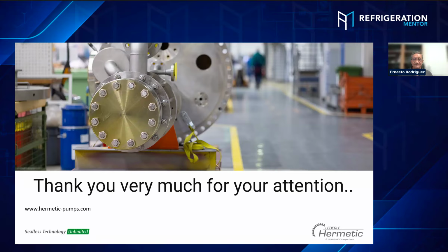Bypasses. Some companies use bypasses, and CO2 is basically critical. They use a bypass when the heat exchanger is not demanding much liquid. They open the bypass and start recirculating the liquid from the suction all the way to the discharge of the pump, and it starts flashing gas. They called me and said, we have problems with those pumps, they are not working. After I went over there and checked the design, I said, this is the problem. You have the bypass on the discharge of the pump, your system is not demanding liquid, and you open the bypass, so you are constantly recirculating the CO2. You heat the CO2 and get bubbles. Those bubbles go to the suction of the pump. Be careful with bypasses, and you're going to have problems with the pump if they control the flow with the variable frequency drive.